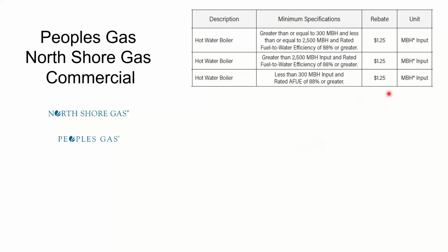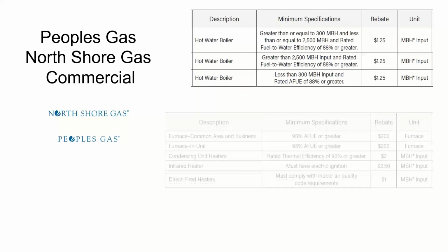Focusing on these, you can get $1.25 per MBH input for 88% or higher, which essentially puts you into condensing. Any condensing boiler will get $1.25 for every MBH of input you have. It doesn't sound like a lot, but when you multiply it by 1 million BTUs, it becomes a big amount of money. I have no idea why we have these three rows still; it used to be different amounts and different tiers back in the day, 10 years ago. Now they're all the same, so essentially you can just put this whole thing in one big column. So all boilers get $1.25 per MBH input if they're condensing.